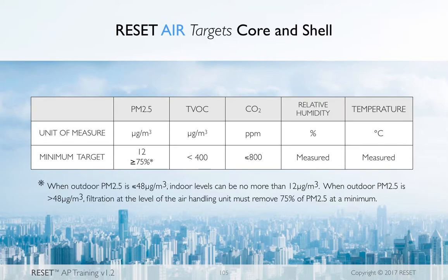So showing that your HVAC system is designed to protect by at least 75% and hold that 75% protection factor through the duration of polluted days is our attempt at making it a reasonable target, but also a significantly important one, because a protection of 75% is something that is noteworthy. A project designed that way deserves to have a certification.